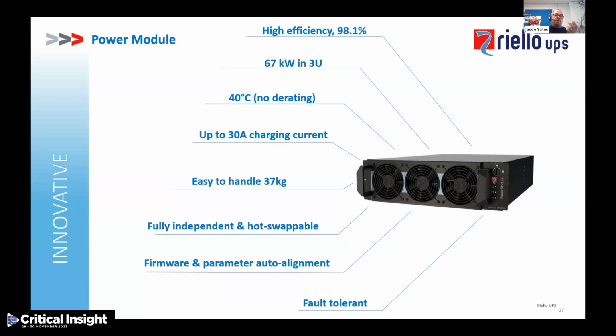It can operate in temperatures of up to 40 degrees C with no derating. And the beauty of this, again, is that it keeps our cooling requirements low. It has a large charging capacity, so it can be partnered with large battery systems, whether that be lead or lithium, whichever. It's easy to handle. Okay, 37 kgs is heavy, but compared to some modules, it's extremely light.